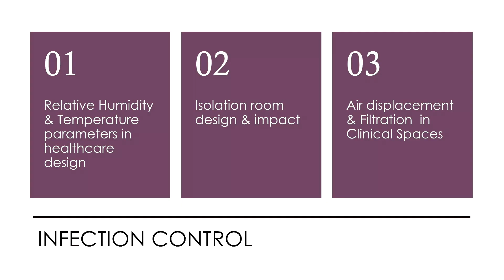So, temperature and relative humidity. What is the purpose of having a temperature of 20 to 24 degrees centigrade, and 18 to 22 degrees centigrade in operating rooms, for thermal comfort and microbial control? Similarly, relative humidity of 30 to 60%. WHO talks about 40 to 60, whereas ASHRAE talks about 20 to 60. Overall, 60 is considered the maximum.